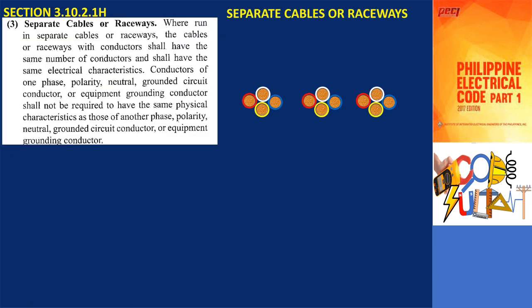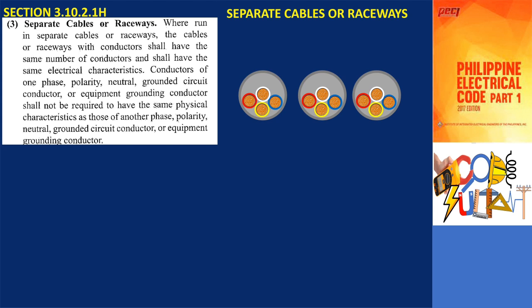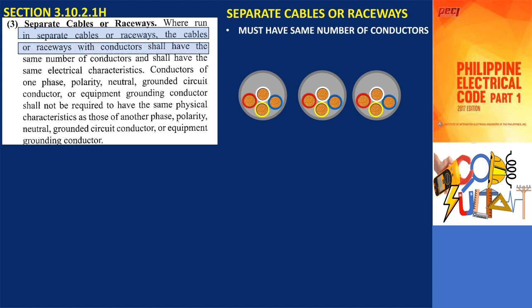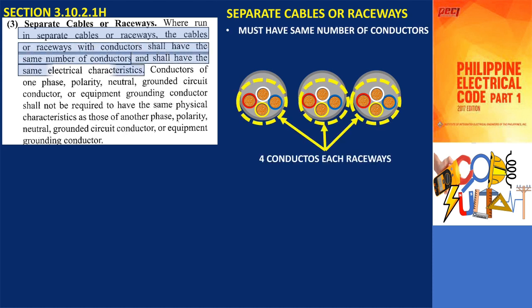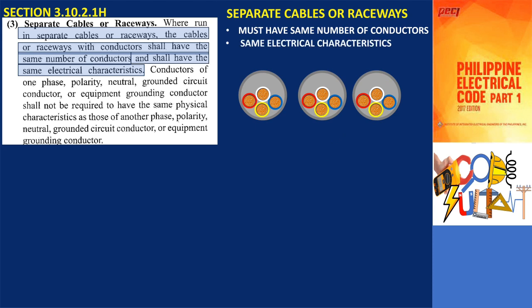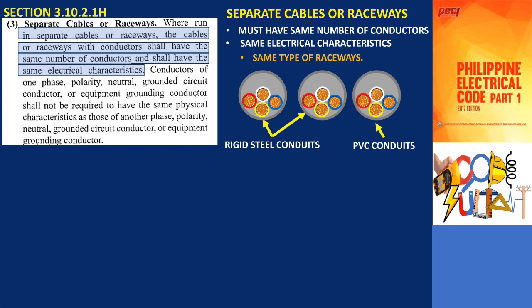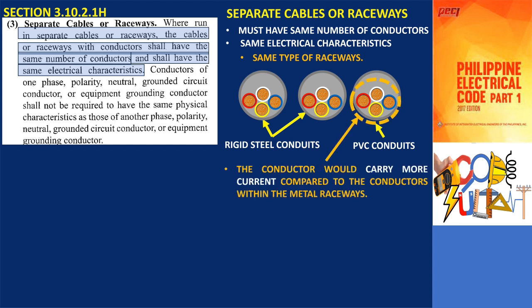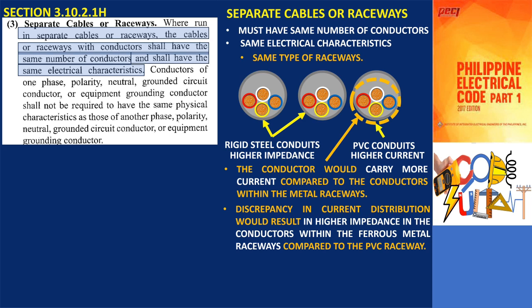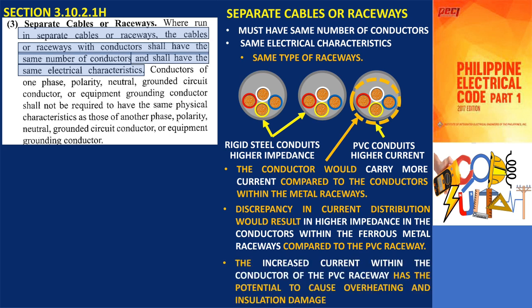Where paralleled conductors are run in separate raceways or cables as specified in subsection 3.10.2.1h3, the cables or raceways with conductors shall have the same number of conductors and shall have the same electrical characteristics. In this context, electrical characteristics specifically refer to properties such as the raceway material. It is crucial to ensure that all raceways within a parallel set of conductors are of the same type. For example, if two of the raceways are rigid ferrous metal conduits and one raceway is a rigid non-metallic conduit, the conductor within the non-metallic conduit would carry more current compared to the conductors within each of the metal raceways. This discrepancy in current distribution would result in higher impedance in the conductors within the ferrous metal raceways compared to the PVC raceway, and the increased current within the conductor of the PVC raceway has the potential to cause overheating and insulation damage.